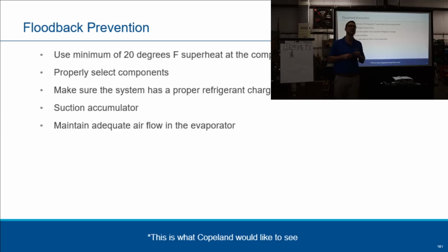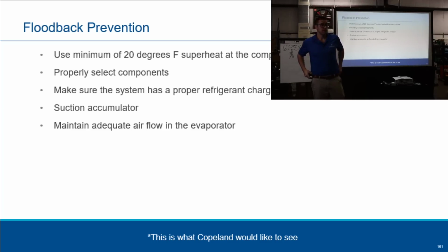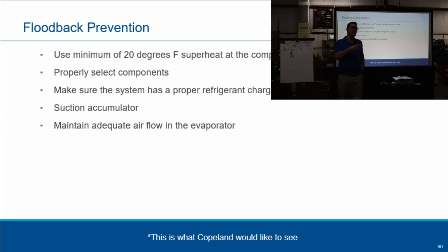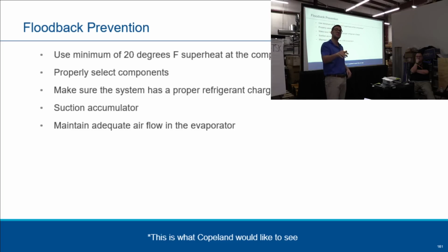Dick, what's too much superheat back at the compressor? You tell me, Dick, what's too much superheat? I always thought over 40. Over 40? Yeah. Depends on the compressor, right? Depends on the temperature of the refrigerant coming back. Yes, there can be a max. 65. Yeah, 65. But it all depends, once again, on the compressor, because I'm going to show you in a few minutes that if you go over 20 on some, you're going to get a failed compressor. You go over 40 on some, you're going to get a failed compressor. It all depends on the application and the compressor you're using.